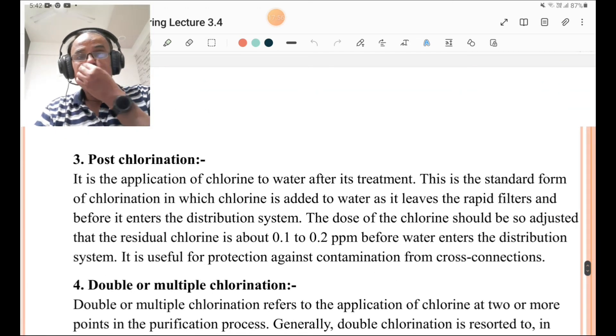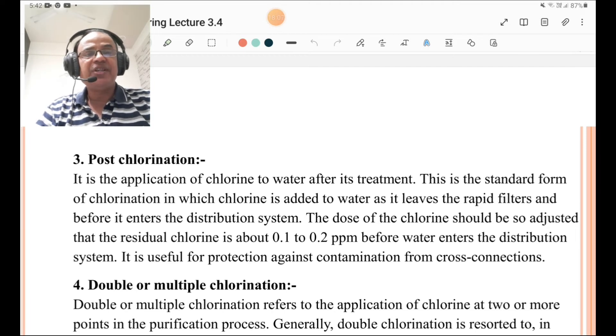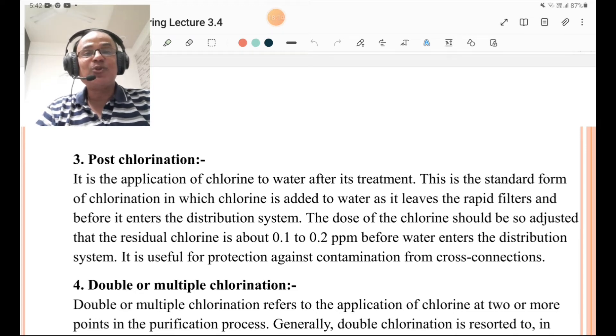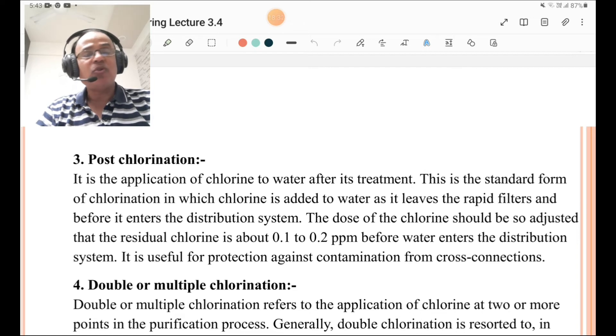Post-chlorination, as the name indicates, is the application of chlorine to water after its treatment. This is the standard form of chlorination in which chlorine is added to the water when it leaves the rapid filters and before it enters the distribution system. The dose of chlorine should be adjusted so that the residual chlorine is about 0.1 to 0.2 ppm before water enters the distribution system. It is very useful for protection against contamination from cross connections.